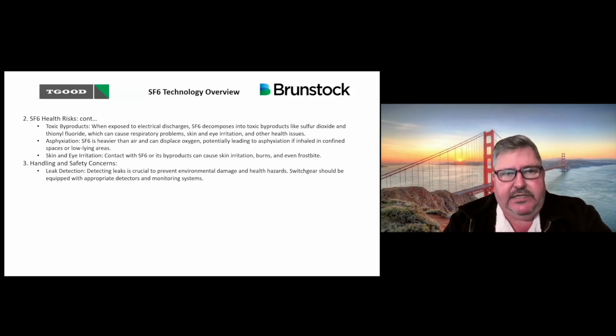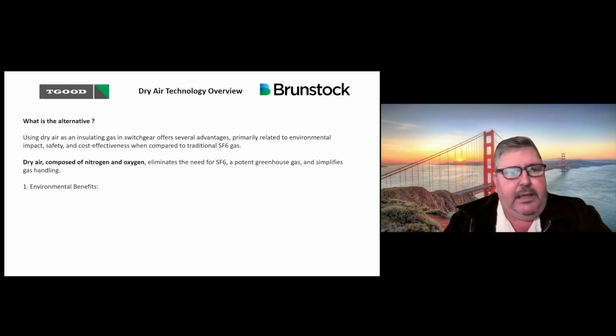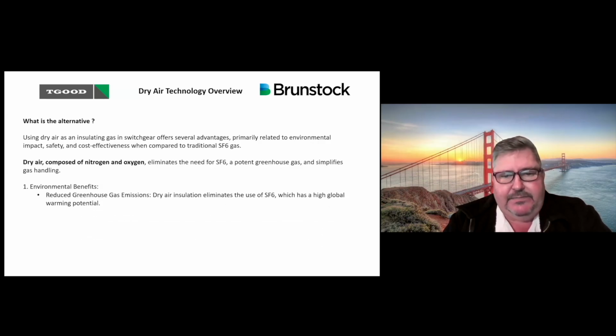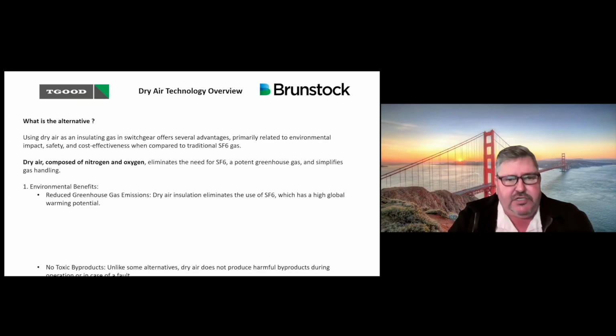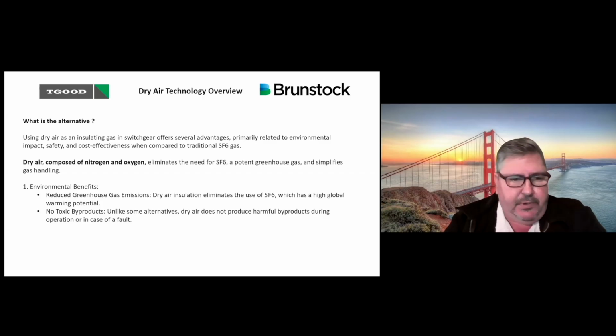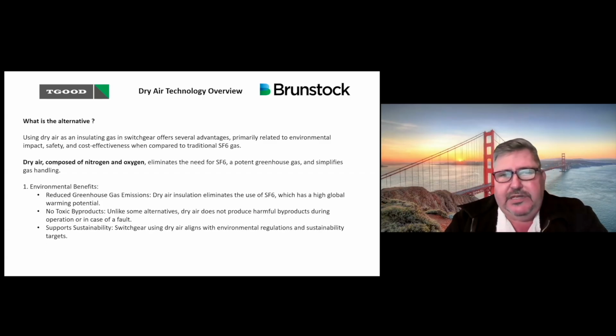So what are the alternatives in the industry? That's where TGOOD has moved into new ventures, using dry air insulation as the medium in our switchgear. This has low, or actually no, impact on the environment. It's very safe and cost effective. For the environmental benefits, it reduces greenhouse gas emissions in the atmosphere, and there are no toxic byproducts created while using dry air. Dry air also aligns with the environmental regulations that we need to move into. As you know, the whole of Europe needs to move away from SF6 gas by 2030, and we are also slowly following that trend, providing green energy solutions.